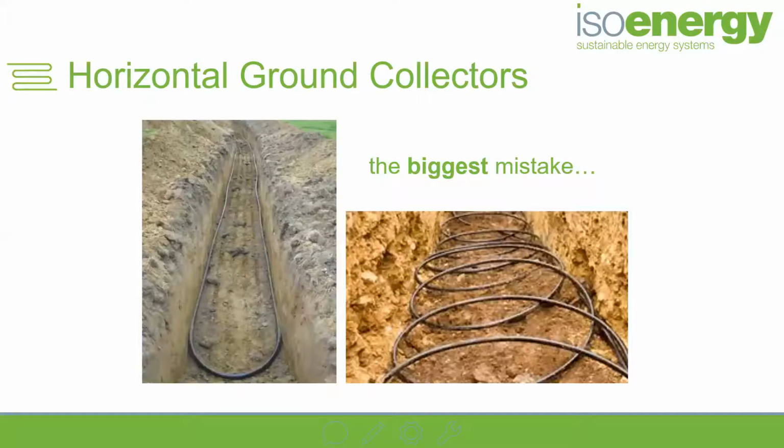This is the single biggest mistake, and my colleague next week will go into more detail on this when he's talking about collectors for ground source heat pumps. But it's coiling pipework on the right hand side versus how you should install pipework on the left hand side, which is a single run of pipe looped back on itself. The reason, if you look at the cross section of that from a bird's eye view, is that you have 4 times more pipework in the coiled version per square meter of earth.